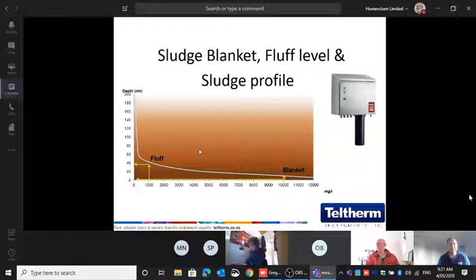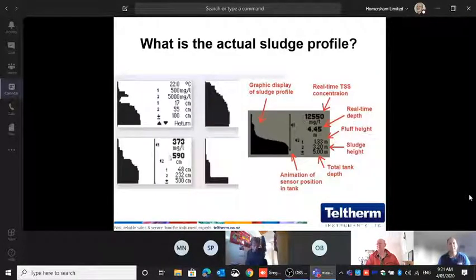This is what the unit basically outputs. So you give it a value for the fluff level and you give it a value for the blanket level. When the unit goes down, there are two outputs, one will be the fluff output. It will tell you where it finds, in here, 1,000 milligrams per liter. And when it hits 1%, it will tell you exactly what the height is as well. Outputs number 3 and 4 are basically depth versus concentration or height versus concentration. You can choose that. So basically you see the profile. That's basically how it looks. In your SCADA system, you can actually create this. New Plymouth did a very good job of showing this on the screen as well while the sensor goes down. This is basically what you want, but yeah, if you got this, an ultrasonic will have an issue here because it will see this layer, not the actual layer.